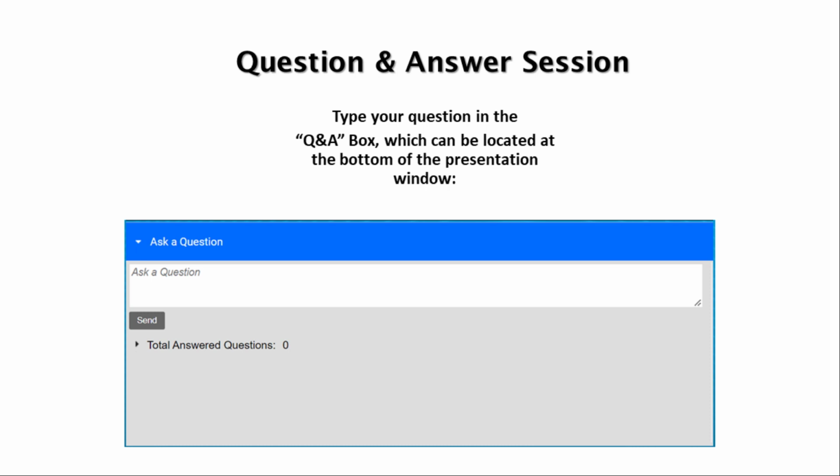Great, excellent info there. So here's your next question. I have methods with 2.6 micrometer and 1.7 micrometer particle sizes. Can I move these methods to 2.7 micrometer and 2 micrometer particle sizes without revalidation? That's right, but you do have to make sure that you meet the system suitability, and then you could also do the verification of the method, as we just described.